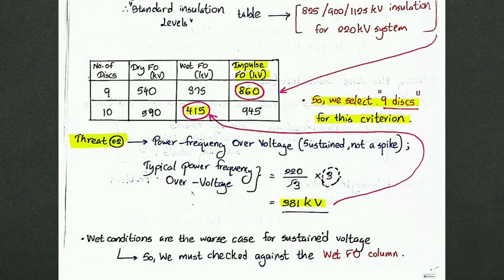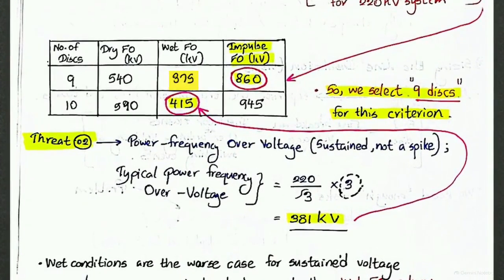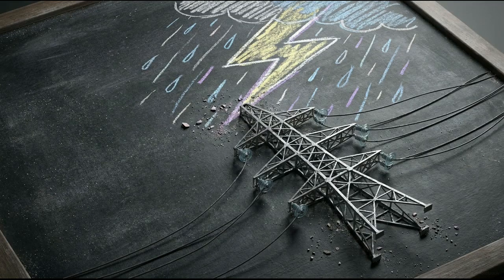Check the 9-disc row again. Under wet conditions, it only holds off 375 kilovolts. That falls short of our 381 kilovolt requirement. To guarantee the line won't flash over during a storm, we have to bump our design up to 10 discs. Dry conditions do not represent the total operational reality. Sizing insulators correctly requires anticipating the harshest physical environment your hardware will actually face.